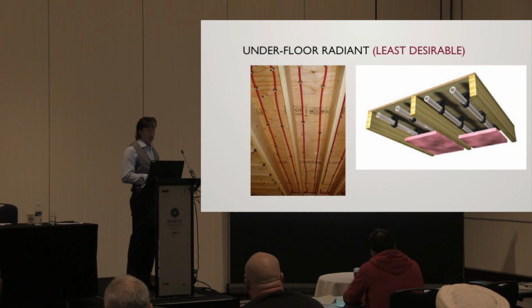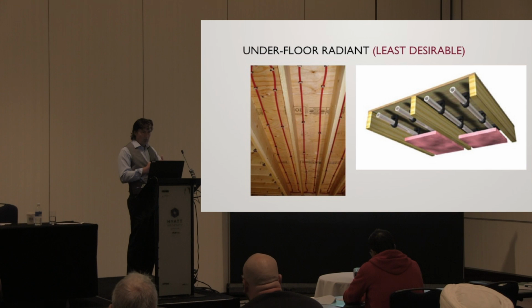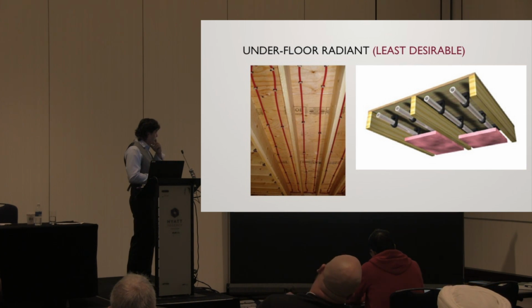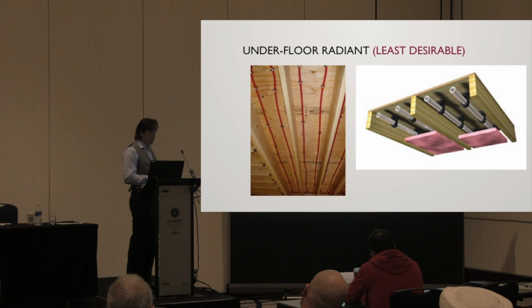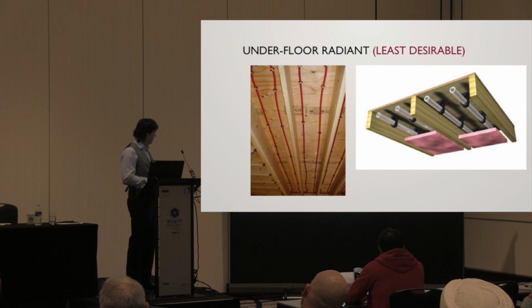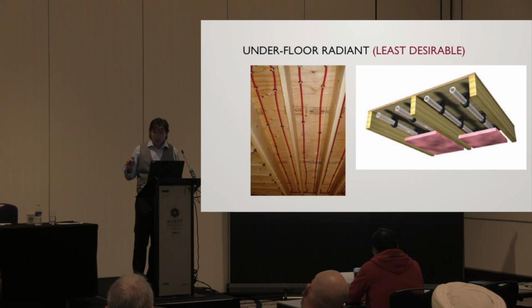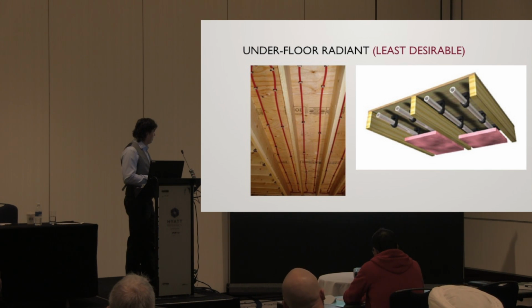So once you get nice hot water, and it's going to be hot water because we've got to heat the room above, think about how we're actually transferring that heat. Radiant needs to have conduction. Our water flows through the tubes, and the heat is transferred through the pipe into the concrete through conduction, and then we're radiating from there. So if I'm trying to conduct heat from this pipe to this wood, it's a round pipe, so really only the top surface of it is actually touching the subfloor, so not the greatest thing. You've got to use heat transfer plates. All it does is increase the surface area. So if I wanted to heat this space with this type of heating, the supply water temperature that I would have to put through there might even go beyond the condensing boiler's comfort zone of efficiency. So not a great way to, if you're going to go to this length, go ahead, put the heat transfer plates in there. Seen this before too.